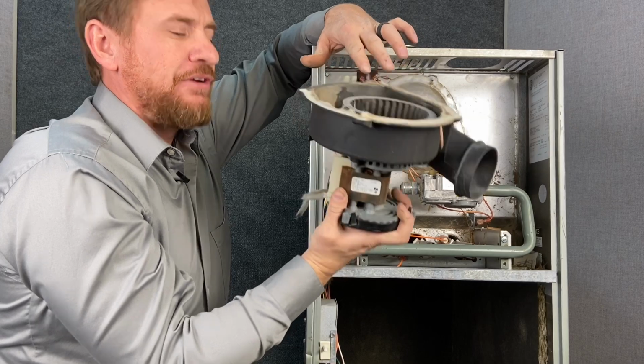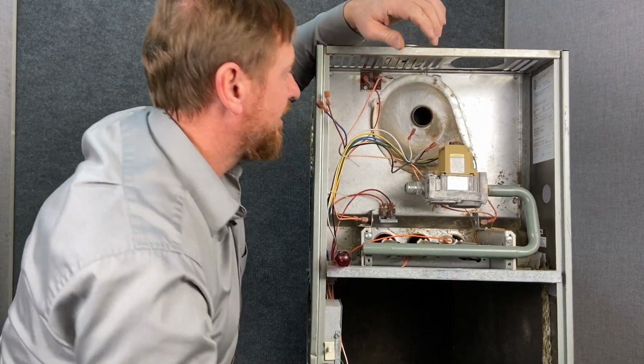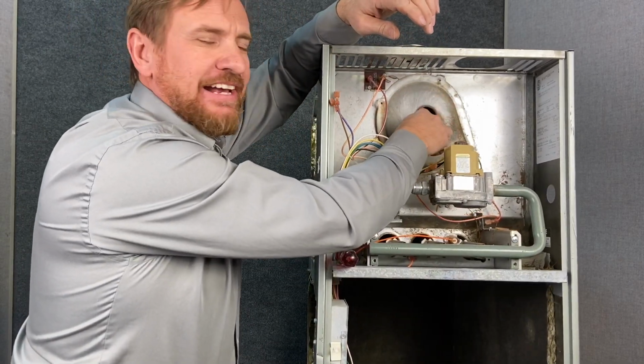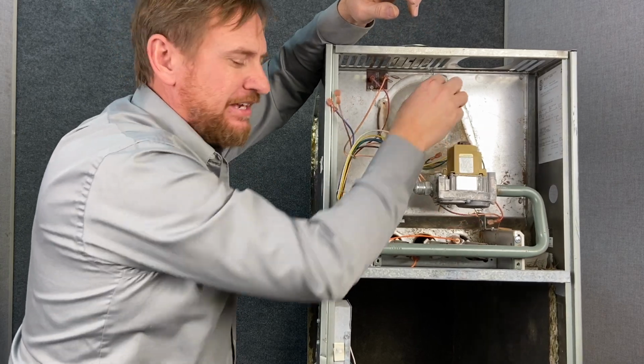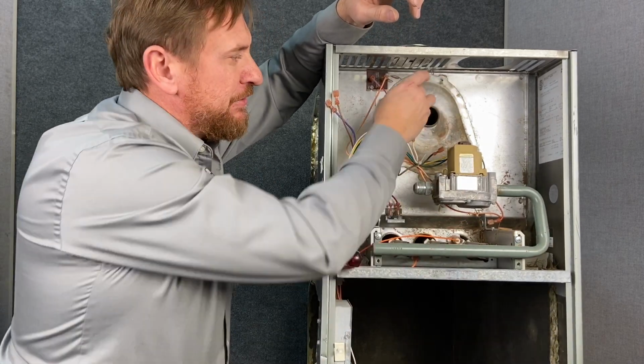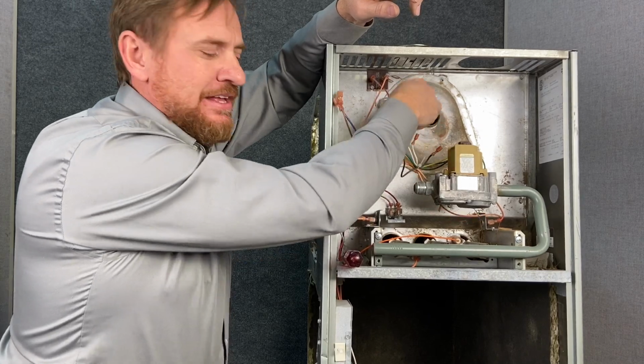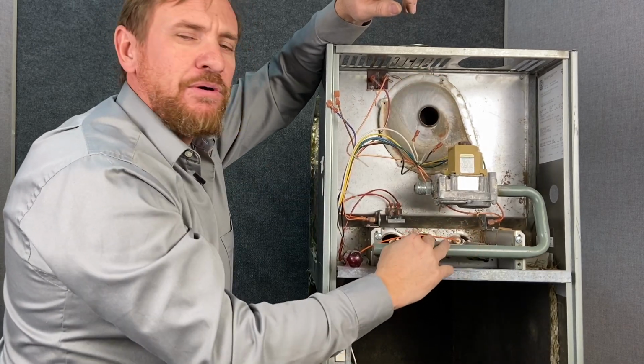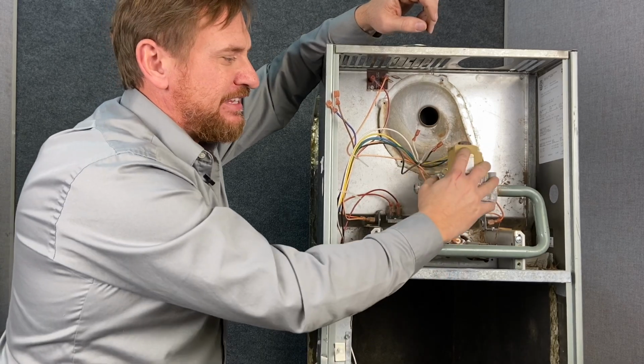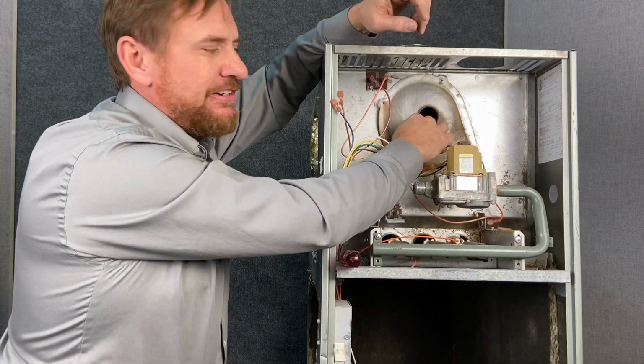Now, this motor here runs and it pulls an exact amount of air, and this hole is a very precisely made hole. So we know if we're moving this motor at that RPM, we know exactly how much air we're pulling through here. That's why these new types of jets don't require any kind of air adjustment. If you set the gas pressure, the air factor is already set for you.